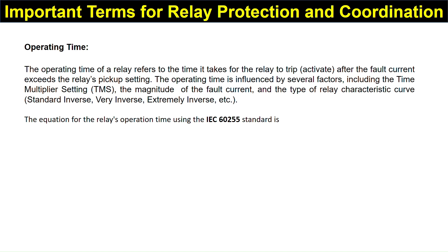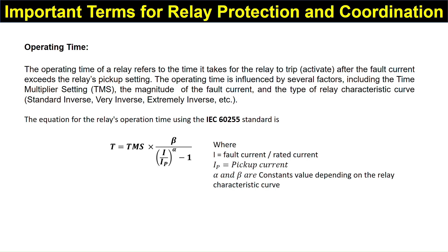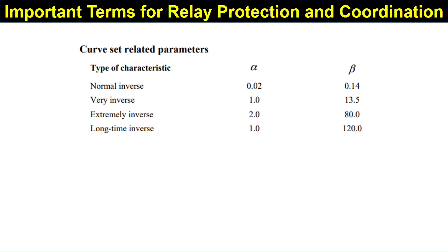The equation for relay operating time using the IEC 60255 standard is: T = TMS × β / ((I/Ip)^α − 1), where I is the fault current, Ip is the pickup current, and α and β are constants depending on the relay characteristic curve. For normally inverse characteristic, α = 0.02 and β = 0.14.